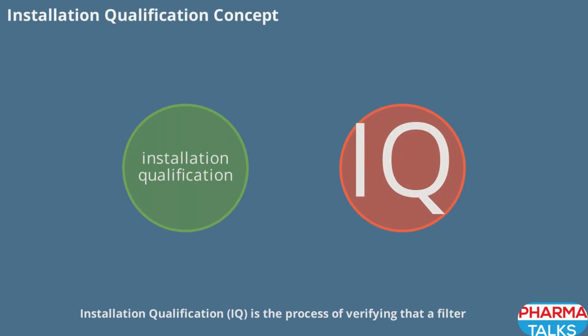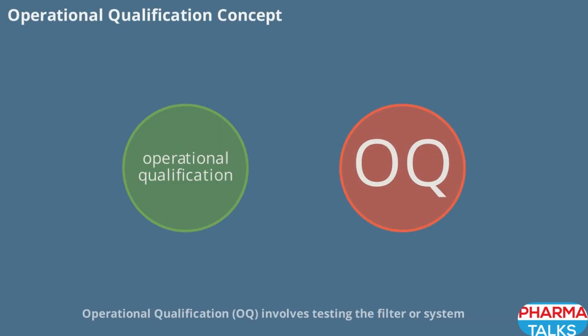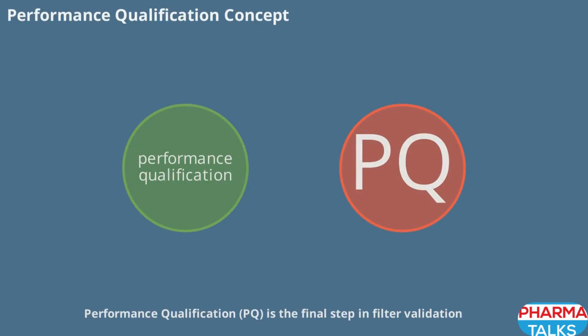Installation qualification (IQ) is the process of verifying that a filter or system is installed correctly according to manufacturer and regulatory requirements. Proper IQ is the first step in ensuring ongoing filter performance and compliance. Operational qualification (OQ) involves testing the filter or system under normal operating conditions to ensure it performs as intended. OQ is a critical step in the validation process for cleanroom filters. Performance qualification (PQ) is the final step in filter validation, confirming that the filter maintains required cleanliness levels during routine operation. PQ ensures that the cleanroom environment remains compliant over time.